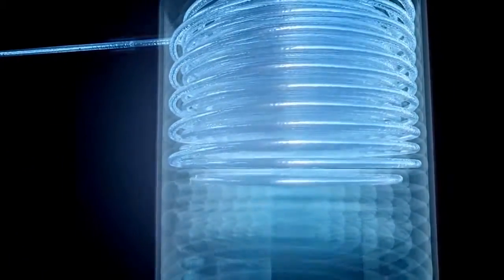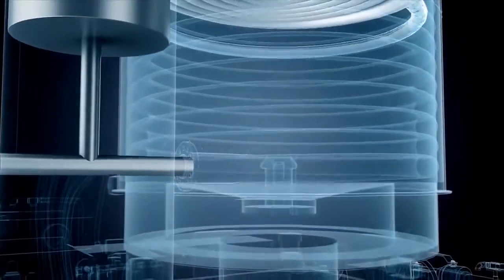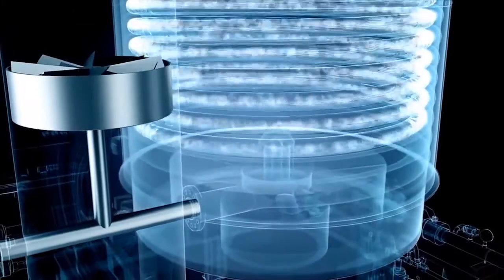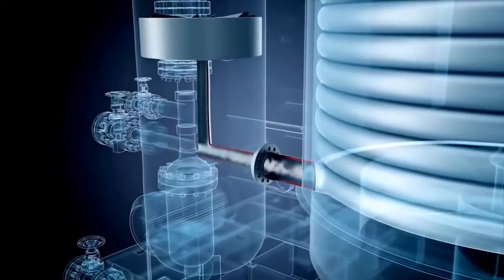Heat travels upwards over the coil in the opposite direction to the flow of water, and somewhere inside the coil, steam is produced. The flow then goes to the special Clayton steam separator, which works by centrifugal force that creates a vortex to guarantee the best quality dry process steam.